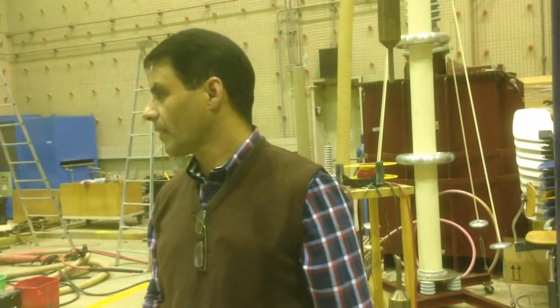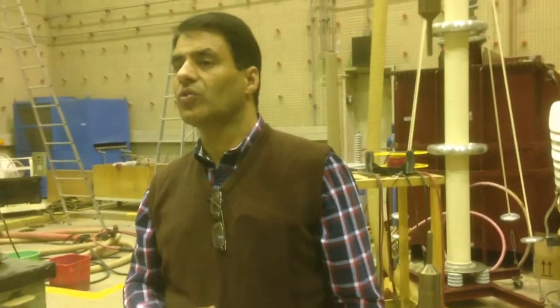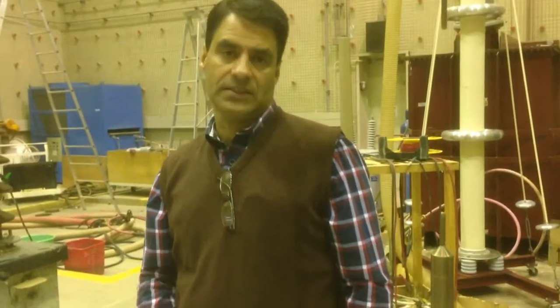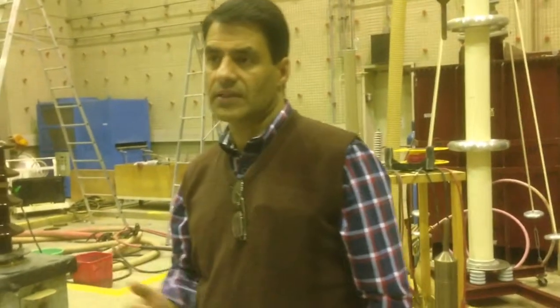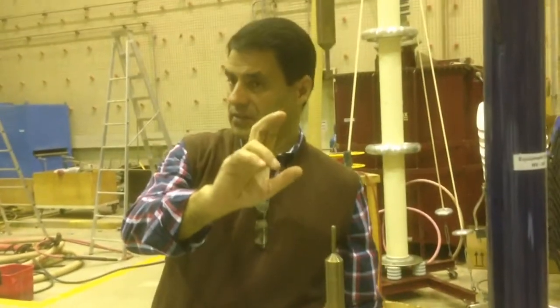Now, what is this VT curve used for? It's used to design protection schemes. When you have a substation, you have a VT curve for the protective device and for the protected object.